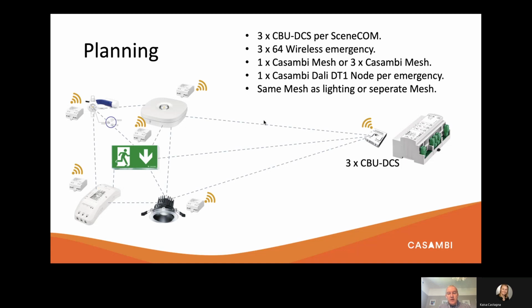And so from one controller, you could have up to 3 CBU DCSs, and those 3 CBU DCSs relate to 3 times 64 wireless emergency luminaires. So it's possible to have up to 192 in total connected back to the SceneCom controller at any one time.